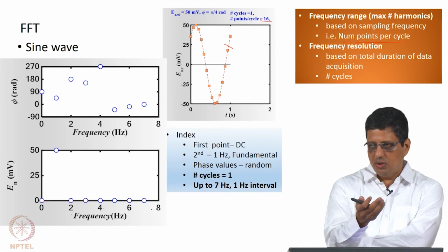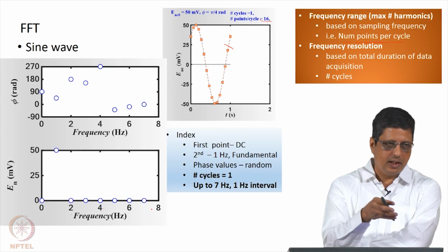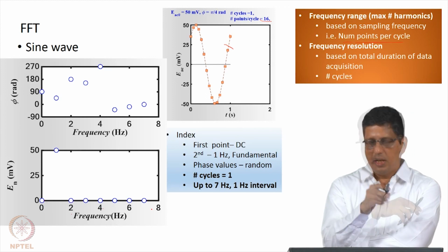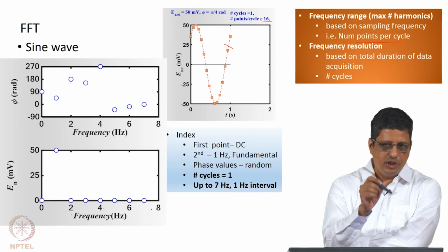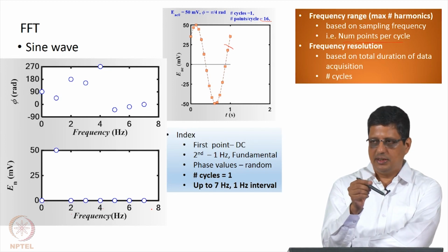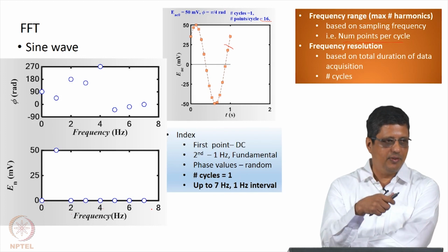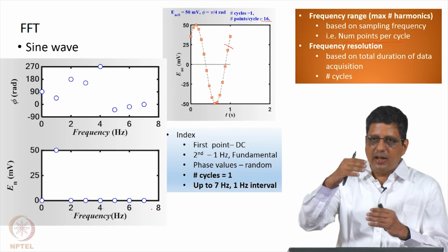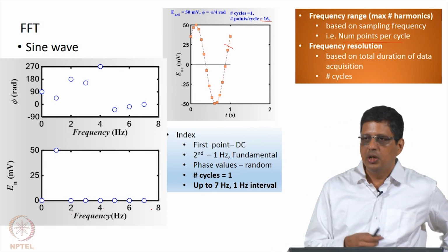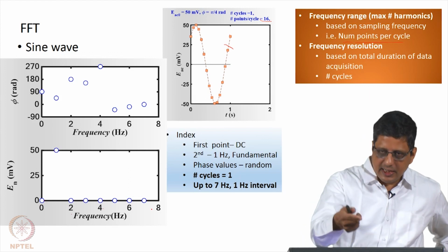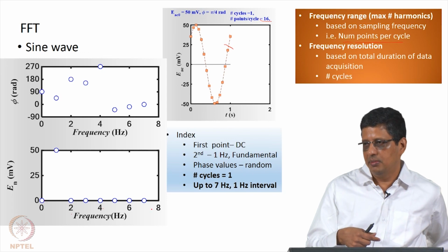Now when you actually take data, software sends a command, usually goes to a board, data acquisition board, collects data. You would say take data at this interval for so much time, and there is a clock within the chip or board which is used to collect at those intervals. It senses all the time, but it will save data at particular intervals. That is stored in a buffer and then transferred to the main CPU or to the hard drive. It does not send a command 10 milliseconds later, send another command from the operating system.